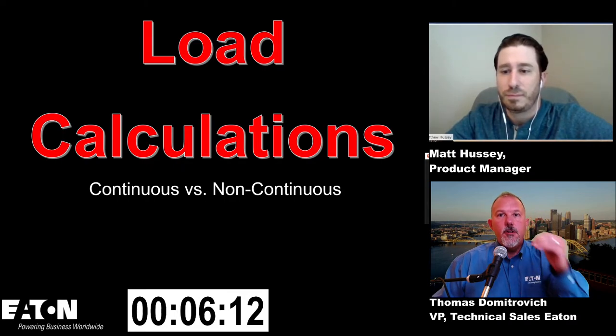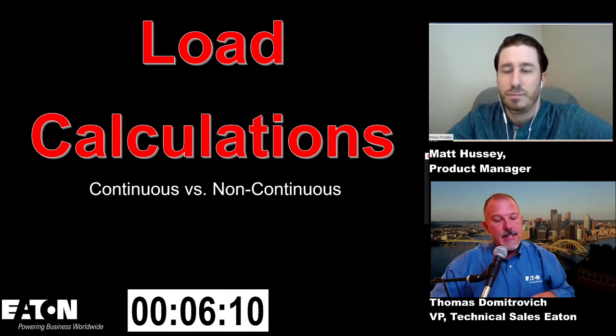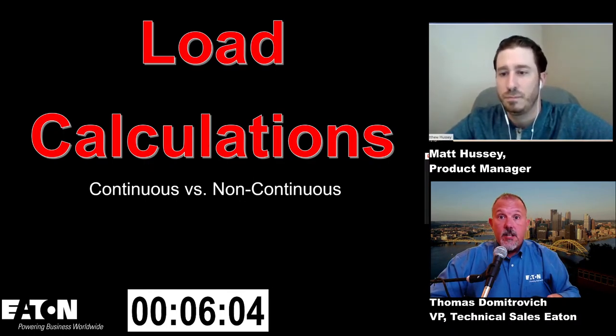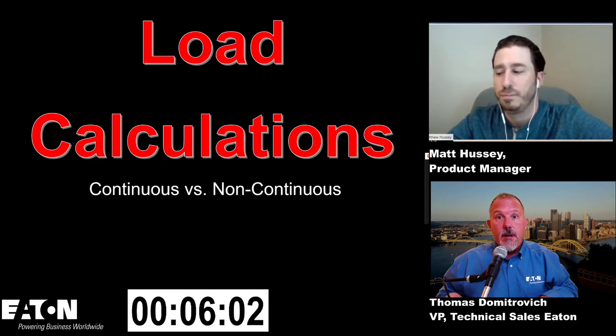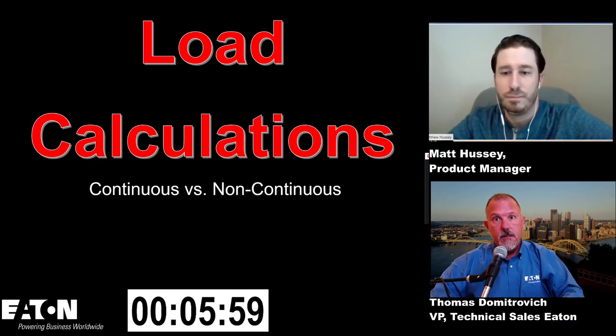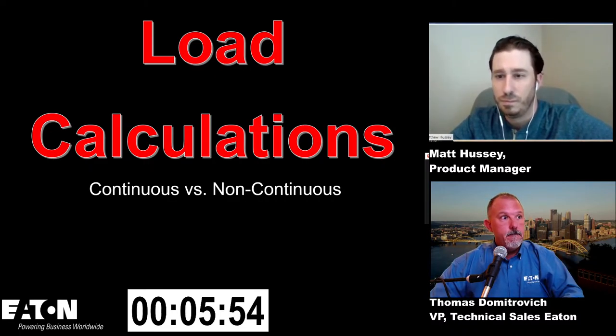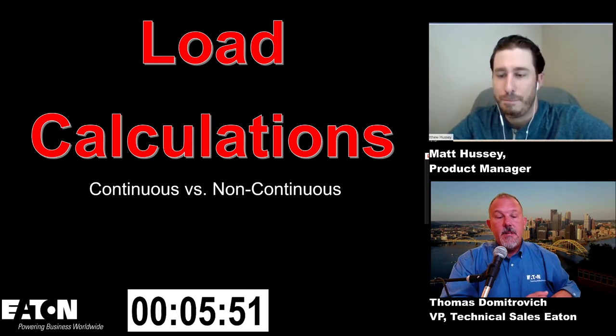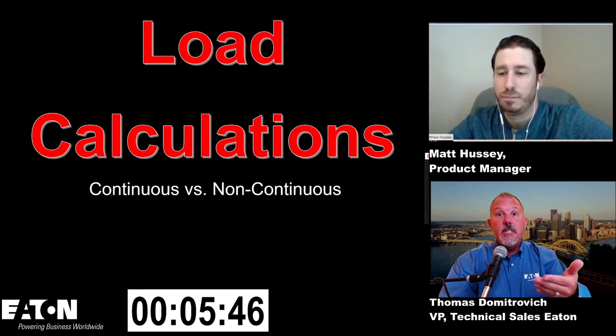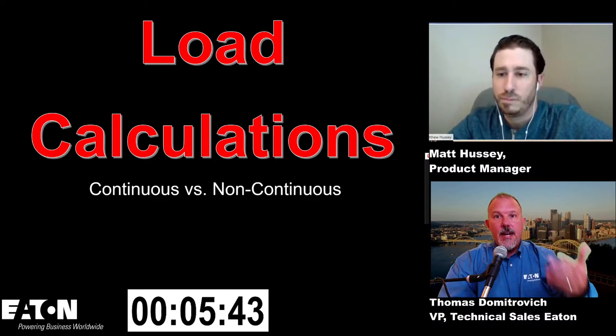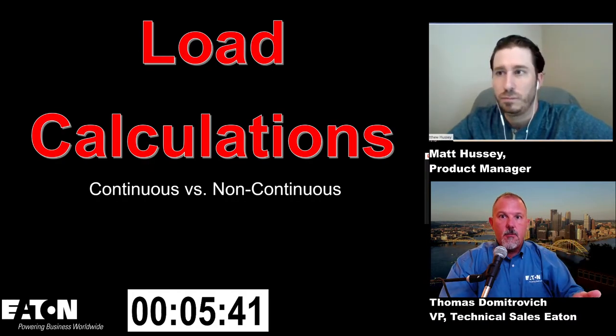Right. So a circuit breaker is tested per UL 489 to its current. If it's a 100 amp breaker, it's tested for 100 amps, but the conductor size is based upon the 80%, right? Yep. So my conductor size based on 80% is going to be a larger conductor for that 100 amp load of continuous current. When I go down the road of saying I'm going to go for 100% rated equipment or a circuit breaker, I'm using a smaller conductor, and it's all about heat.